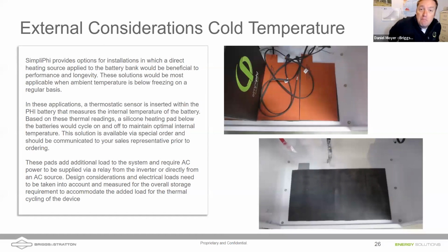There are heating pads. So let's talk about if we have an extreme cold temperature, or maybe we're using those Phi batteries that don't have the ability to talk to a piece of equipment and use their own internal resistance to warm themselves up. We can get heating pads, placed underneath the batteries, ideally on top of a piece of insulation, so you're not spending a lot of energy heating the cabinet but focusing that heat into the batteries. The heating pads need to be special ordered.